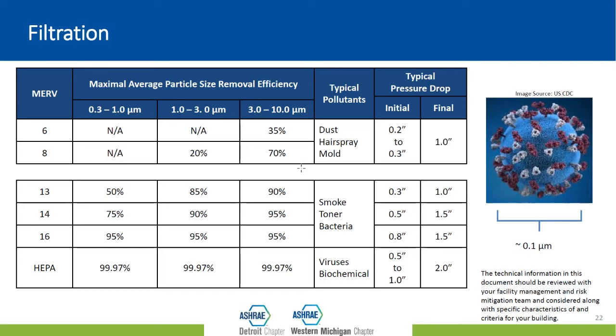So we can see here that as we increase our MERV level, we do get better filtration in each of those size range categories. And in the column titled typical pollutants, we can see what some of these filters typically remove from spaces. A lot of light commercial or residential type equipment might have a filter that's only rated a MERV 6 or MERV 8, right? This is good for removing dust and maybe some molds, but it's not very effective in the 0.3 to 1 micrometer or 1 to 3 micrometer range. And people are interested in looking to move to 13 or 14 or 16 MERV values.